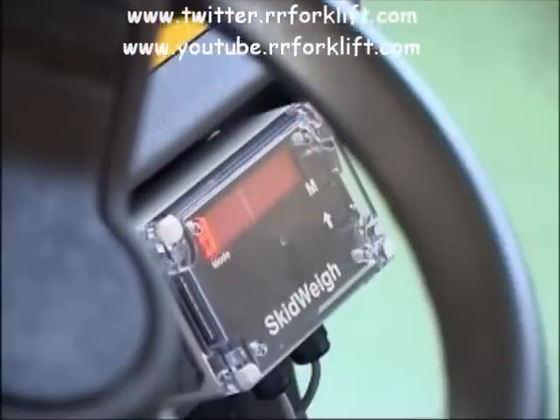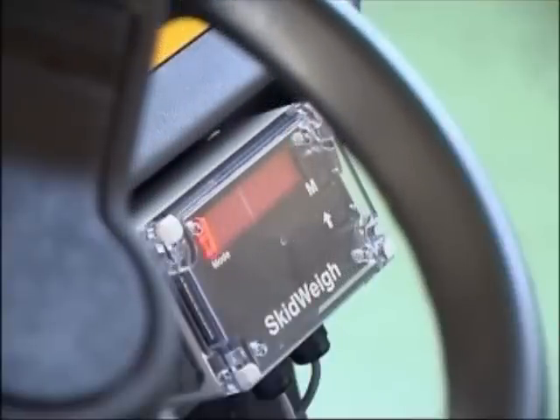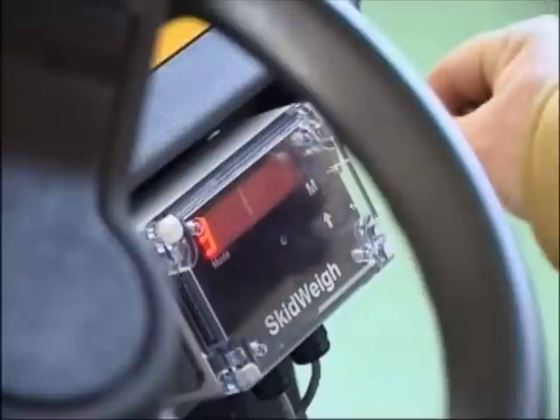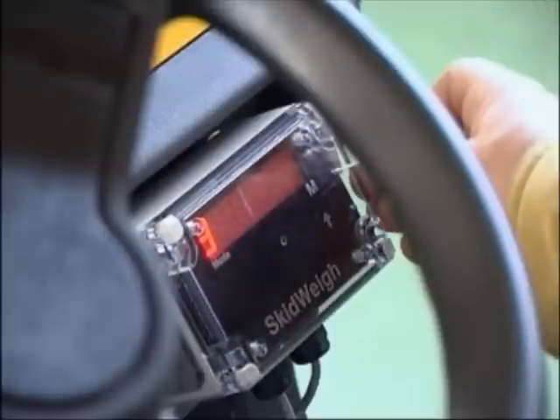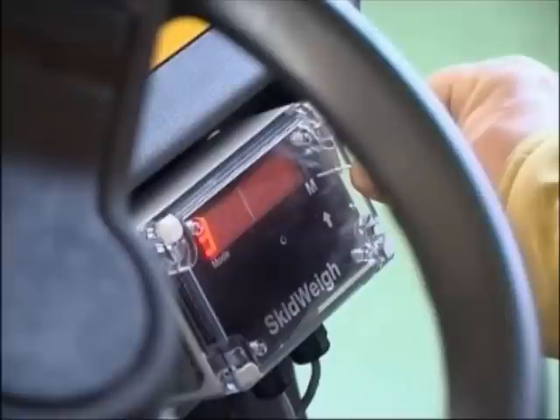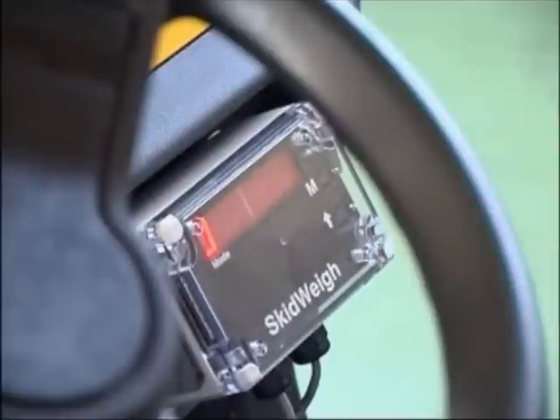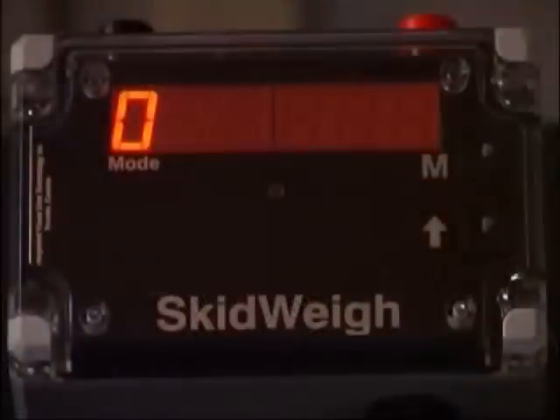While the number 8 is shown on the left side of the display in the mode window, use a paper clip inserted into the small hole to the right side of the letter M, on the right side of the display. Press down and hold for 5 seconds to enter the calibration mode. The mode digit number on the left side of the display will change from 8 to 0. This mode is used to calibrate the empty forks lifted off the ground. If the forklift has any type of attachment, lift the attachment above the ground to get the 0 reading.